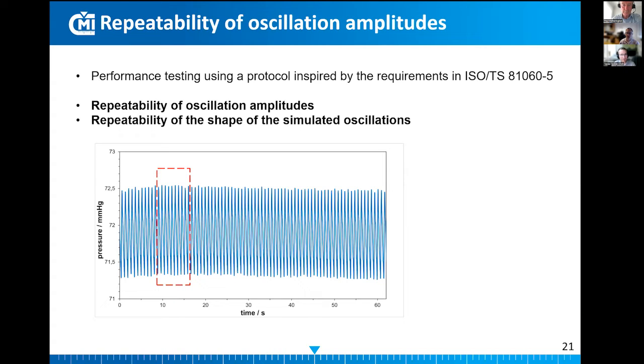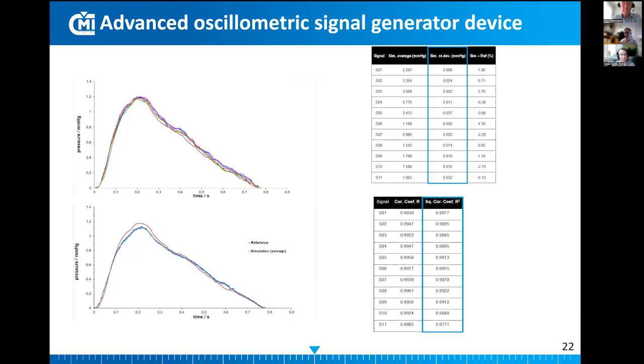After colleagues from PTB developed this device, they performed testing of the stability and applicability of the simulator. The testing procedure was based on the technical specification ISO 81060-5 with 2 parameters evaluated. The first one was the repeatability of oscillation pulses, and the second, the repeatability of the shape of the simulated oscillations. With both parameters tested, the results were very good.